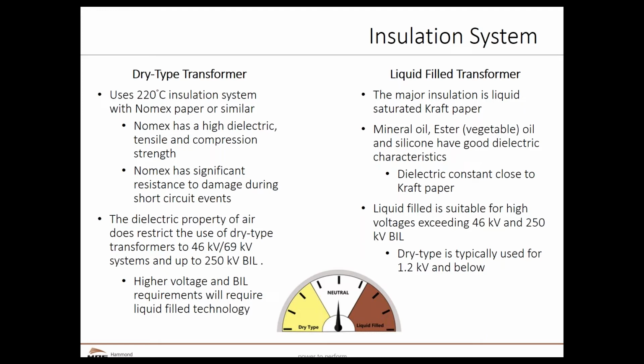Now, liquid filled typically uses what we call kraft paper. It's just thick paper. Paper in itself is not a good insulator, but when you soak it in oil, it works very well. It's very effective. And because of the surface area and because of how the transformers are cooled, liquid filled transformers tend to run cooler. Doesn't mean that they're that much more highly efficient than dry type, but it has a lot to do with the surface area and the cooling fins and stuff like that. And they have to run cooler because they're using paper. At temperatures where Nomex would be like a fall day, paper starts to deteriorate. So they have to run the transformers cooler in order to work. But as long as both transformers are properly designed and cooled, they both should supply you with decades of solid use.